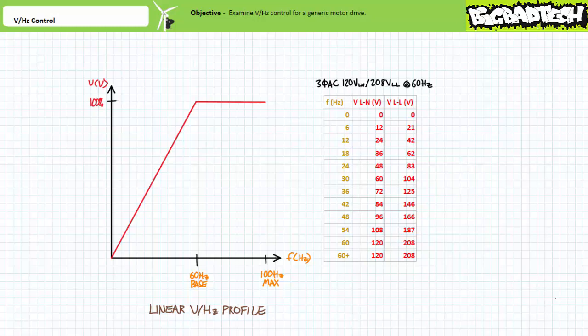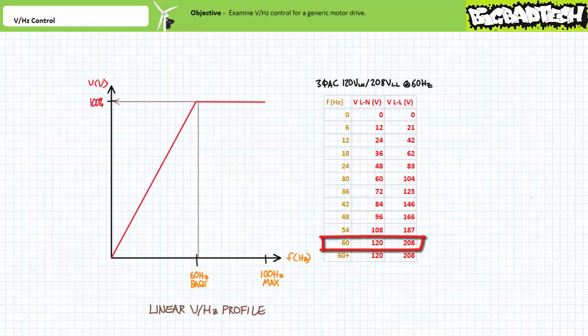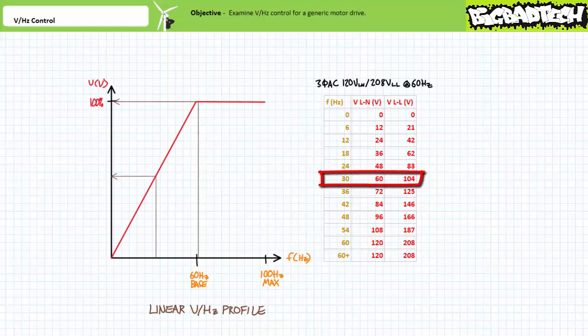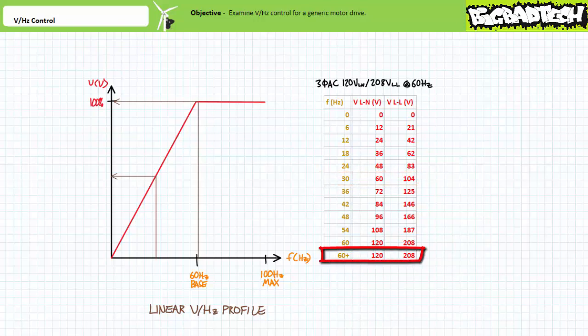A basic graph of volts per hertz control is typically linear from zero to the base frequency, although this isn't always the case and sometimes application-specific volts per hertz profiles exist. This basic linear volts per hertz profile applies zero volts at zero hertz and, assuming a 60 hertz base frequency, full voltage at 60 hertz. If one was to dial the excitation frequency down to half the base frequency or 30 hertz, applied voltage would also be proportionally reduced to 50 percent. Beyond the base frequency, motor drives typically flatline applied voltage at 100 percent up to the maximum frequency.